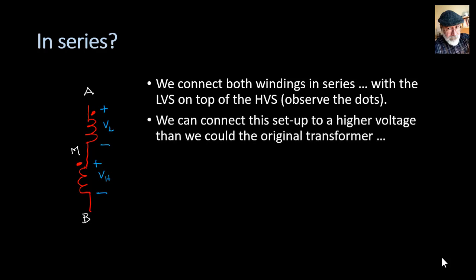We can connect this setup to a higher voltage than we could have the original transformer. We can connect that to a voltage which is the sum of the rated voltage of the high side plus the rated voltage of the low side.